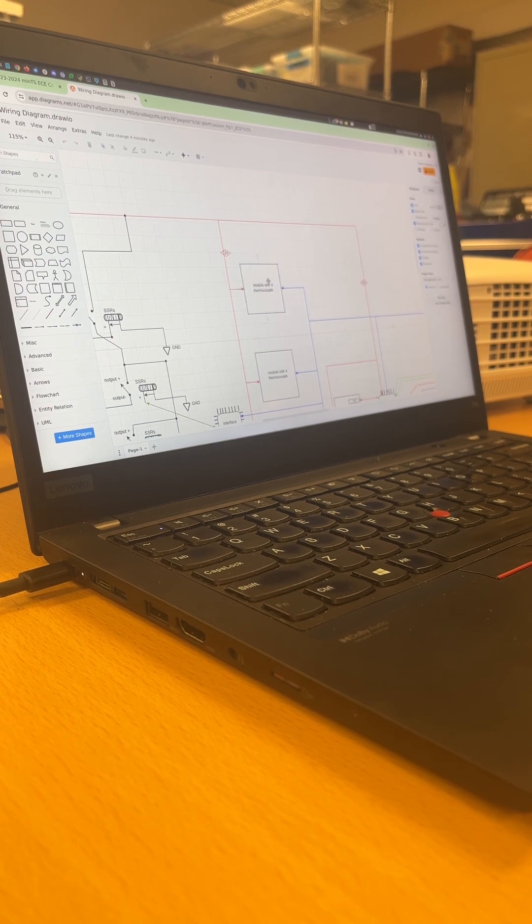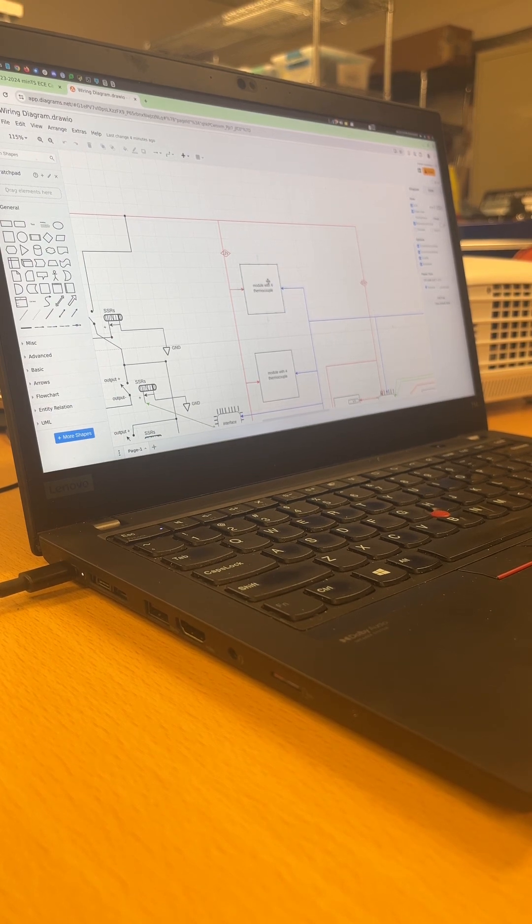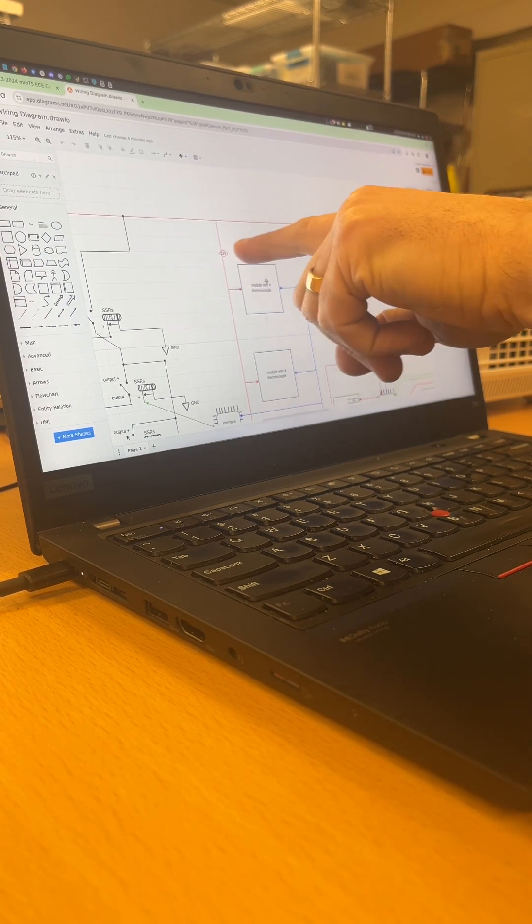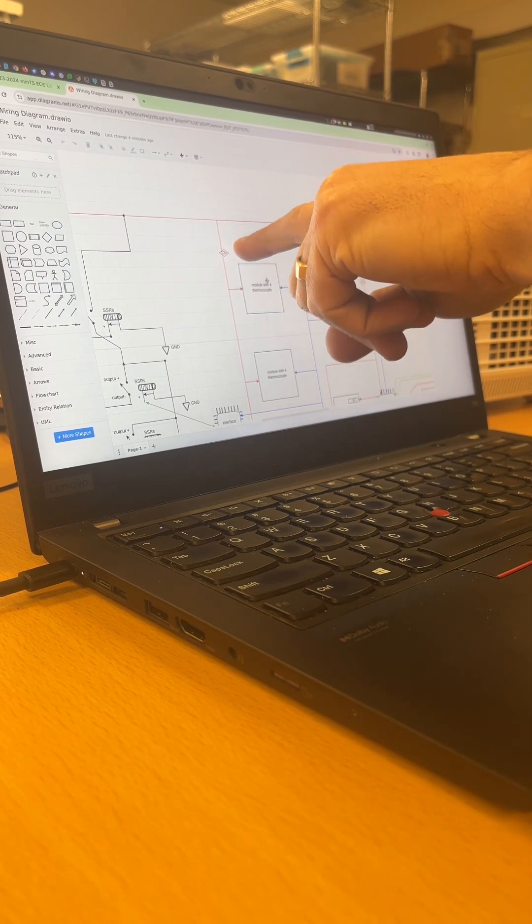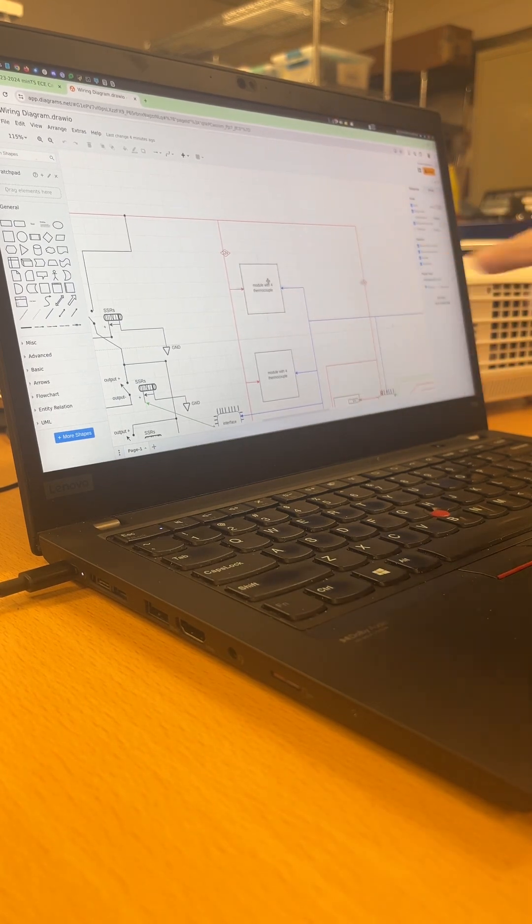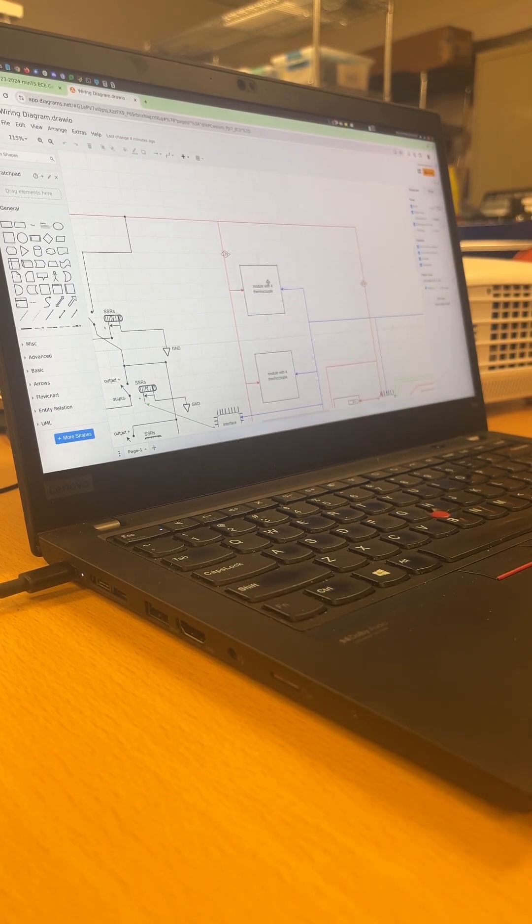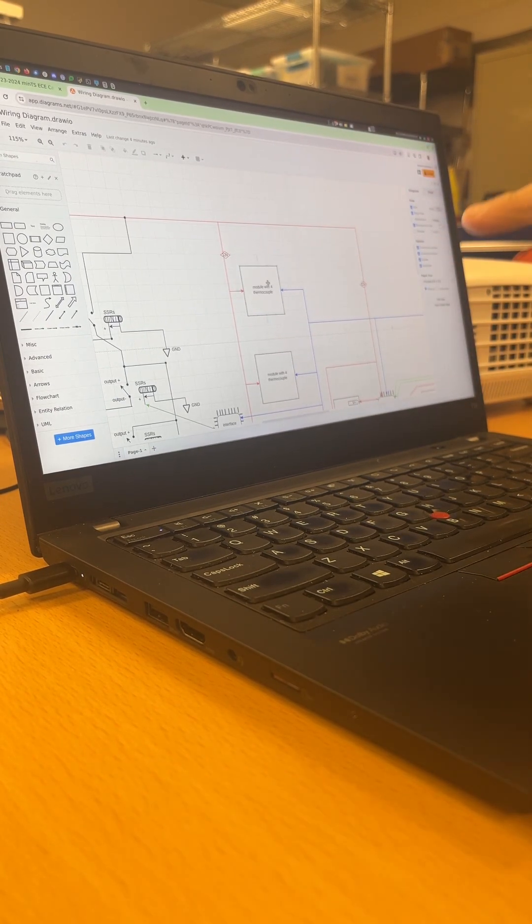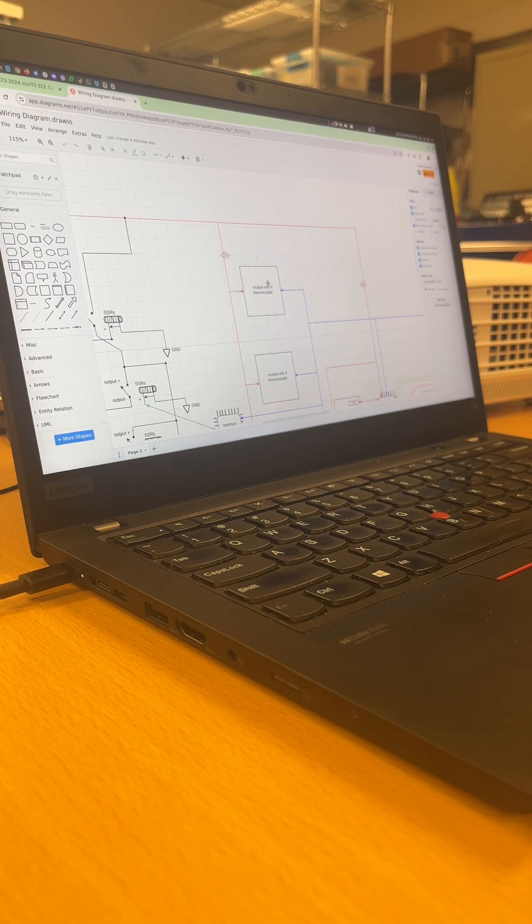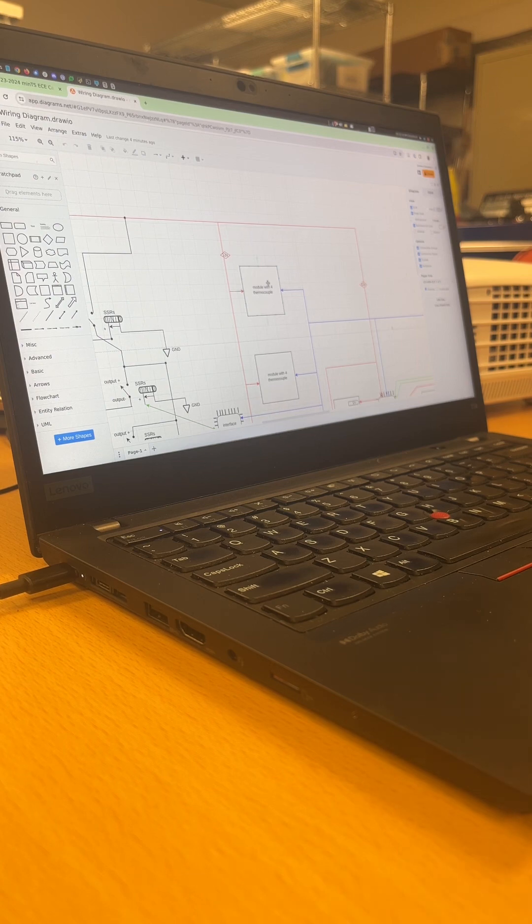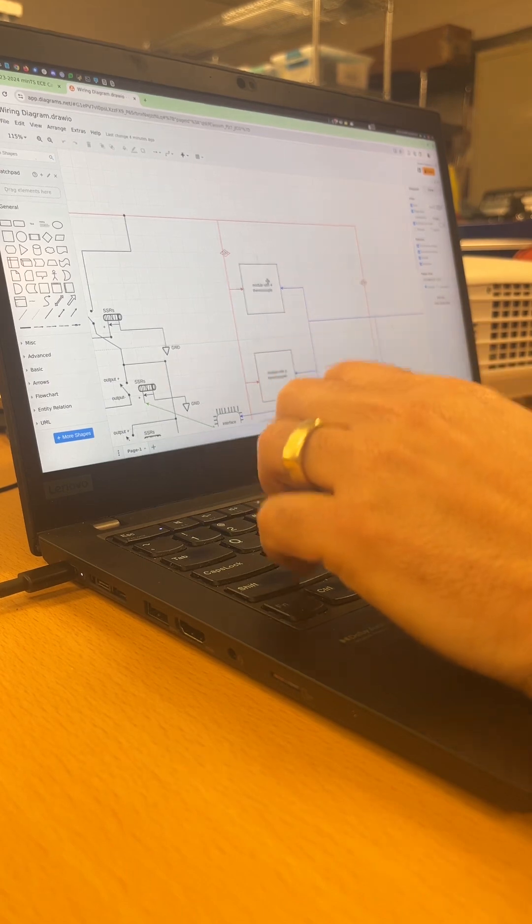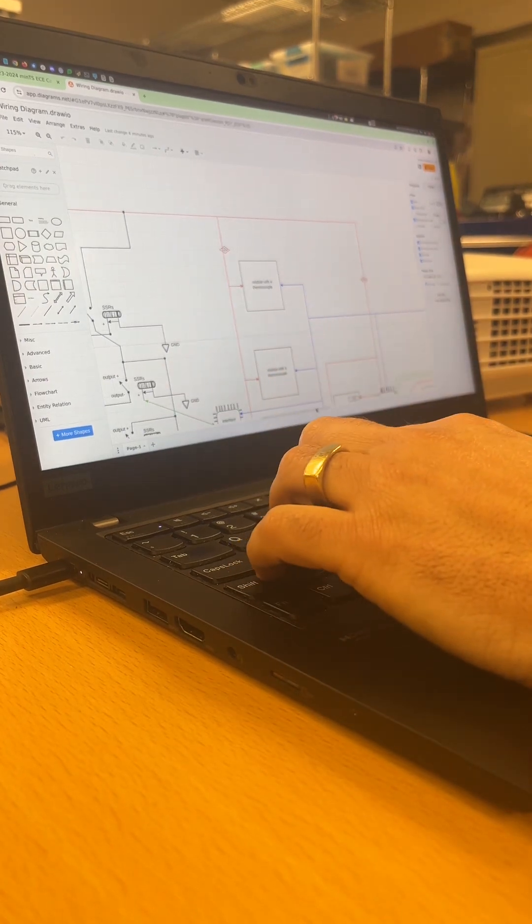So I can say hey, there's a thermocouple on this line or this valve, and it's thermocouple five. Oh, I can go here and see it's thermocouple five and it goes to this interface module. So now I don't have to trace the wires. I can come to this diagram, see it's on interface module five wire three, and now I can fix it or do whatever I'm doing.